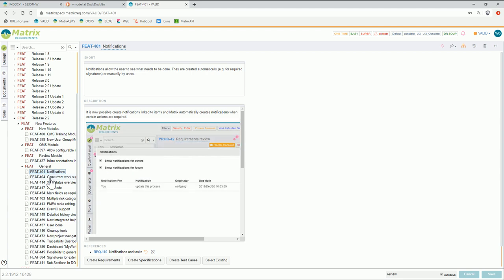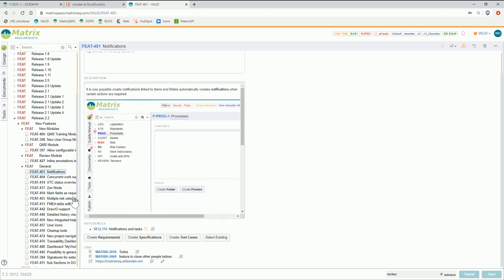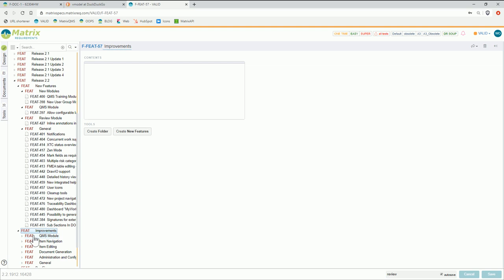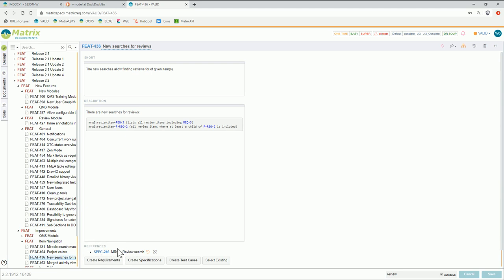In another place we have a little bit more details with an animated GIF, and these are all the changes in the product. What we usually do is just link them on one side to the requirements. If it's a completely new feature, usually it's going to be a new user requirement. If it's an improvement, it's more often actually a change of a requirement on an existing specification. If it's a bug fix, usually the requirement and specifications were correct, so it will actually link to a test case which needs to be improved so that the next time we test we find the bug.